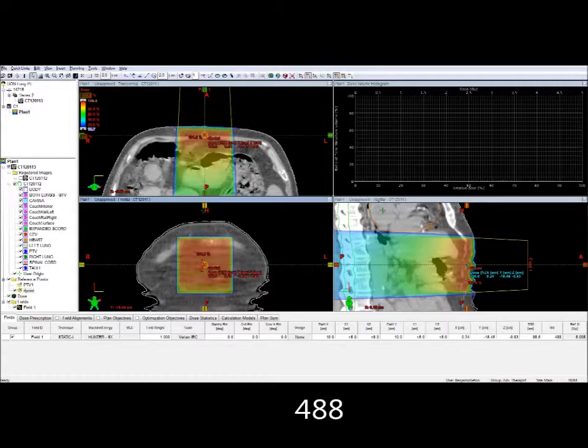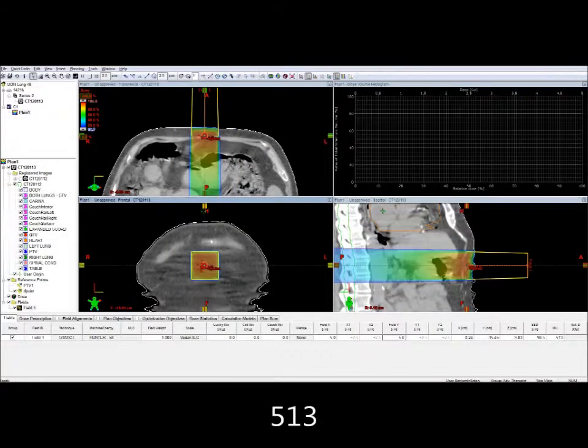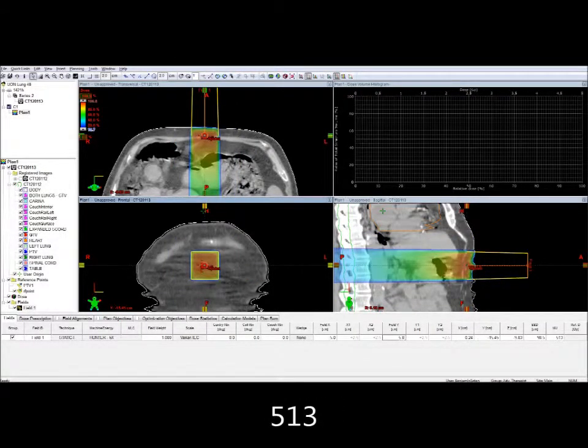Let's see what happens when we halve the field size and keep everything else the same. As you may have noticed, the monitor units have now risen.